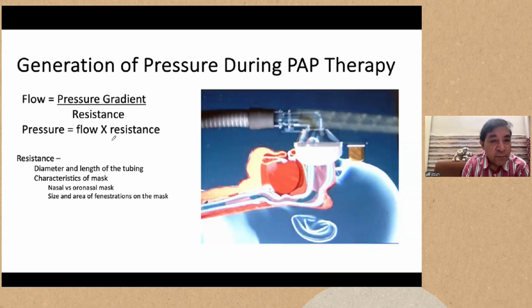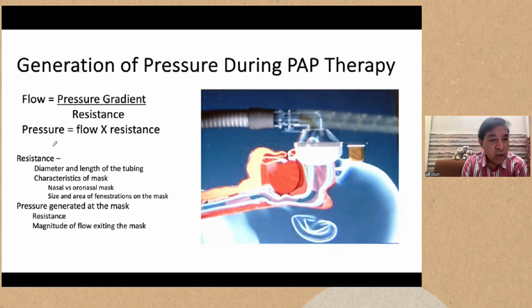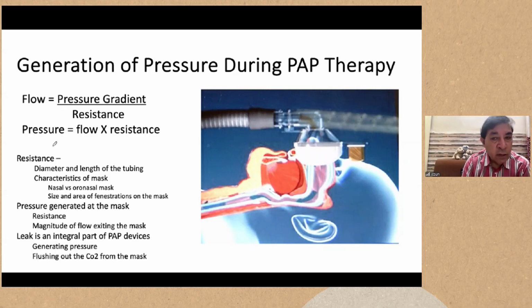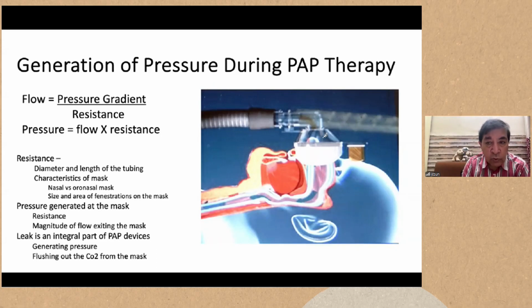So more the flow, more the pressure, because the resistance is constant. Once you use a particular type of mask, the resistance is constant. So more the flow, more the pressure. So that's how this works, on the basis of this principle.